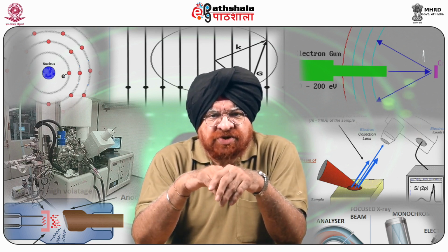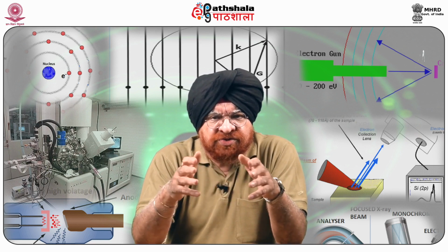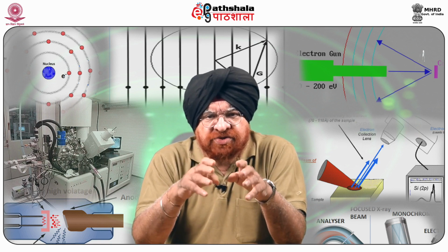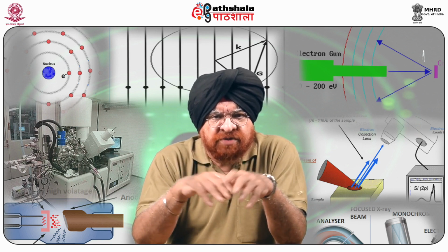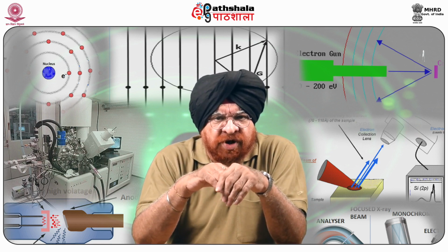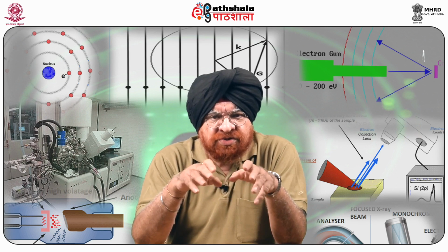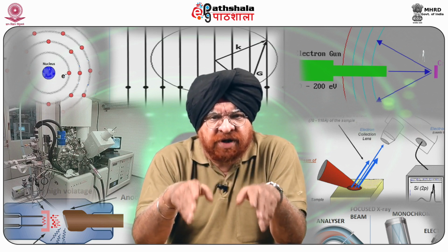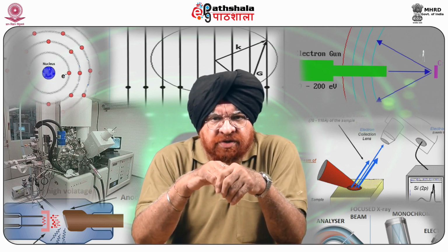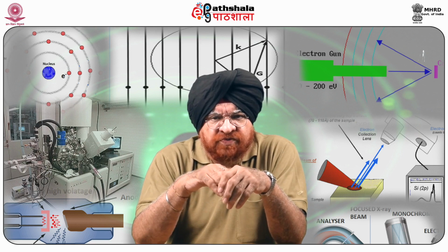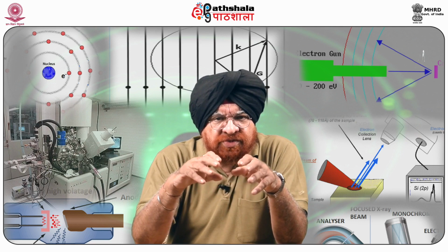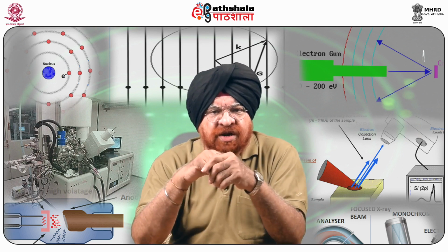It's a tube under vacuum that enhances the incident charges. Here, a secondary electron which strikes a secondary emission material brings about the emission of about 1 to 3 electrons. As soon as an electric potential is applied between the metal plates, the electrons are excited and move to the next metal plate, which again induces secondary emission.